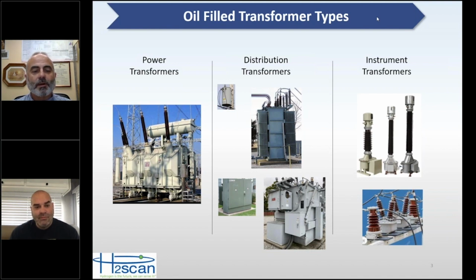So whether you're looking at a large power transformer or a large generator step-up transformer, those are usually the most critical transformers and are the ones that get monitoring first. And as a lot of people put online monitoring in their transformer specs, the monitors come on the transformers from day one, and that's a good thing, so you can monitor those transformers while they're under warranty. If you haven't noticed, a lot of things today don't last as long as they used to, so finding out about problems while the transformer's under warranty is a very good thing, so that hopefully that can get addressed before the warranty expires and you start having problems.